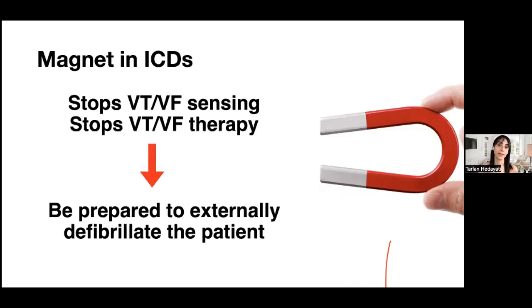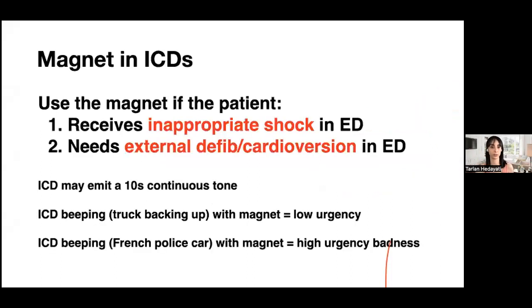If you put that magnet on a patient who has an ICD, you have turned off their life-saving device. Now you better be prepared to externally cardiovert or defibrillate that patient, because the device will no longer work. So it's very different. In a pacemaker, when you put the magnet on, it's going to fire up the pacemaker. With an ICD, when you put that magnet on, you are suppressing the ability of the ICD to cardiovert or defibrillate VTAC or VFib, so you will have to do that. Make sure you've got those pads on before you put the magnet on an ICD. I hope that's clear, because this gets a little confusing.